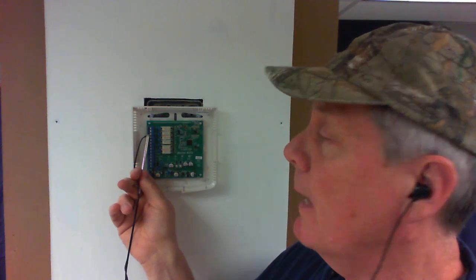So you have to use your best judgment and make your call for your installation of what's the best thing to do with this. You don't have to connect it. It will still work. The control module will still work. Thermostat will still work. It's just constantly going to give you your error message that the plenum sensor is not installed. Once again, we're looking for 10,000 ohms across these two terminals.